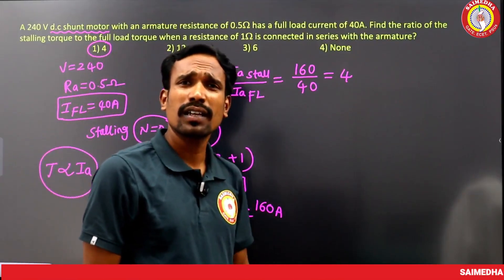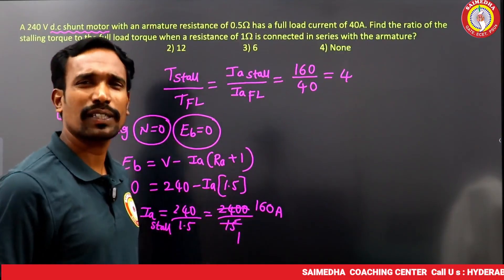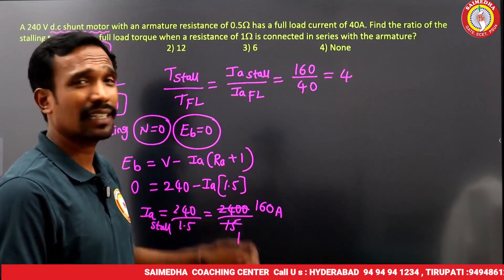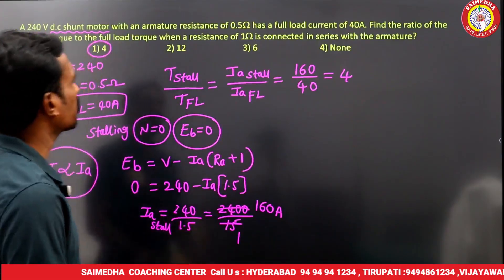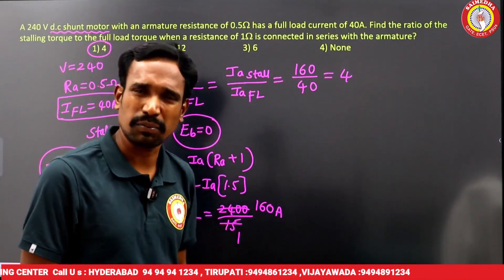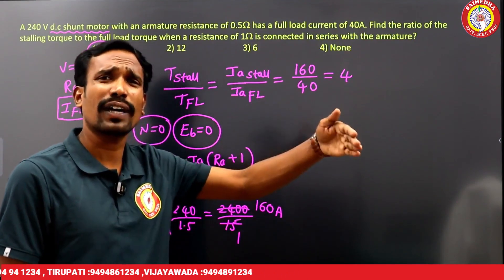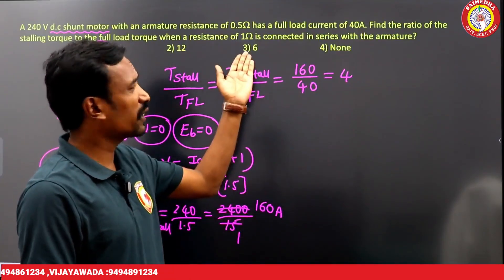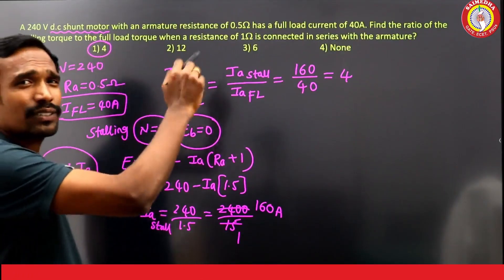The reason the stalling torque is much higher is that when Eb = 0, heavy current flows through the machine — typically four to six times the full load current. For this question the exact calculated answer is four times.